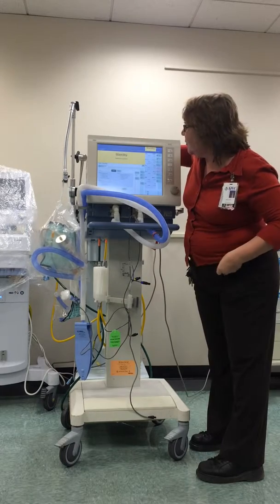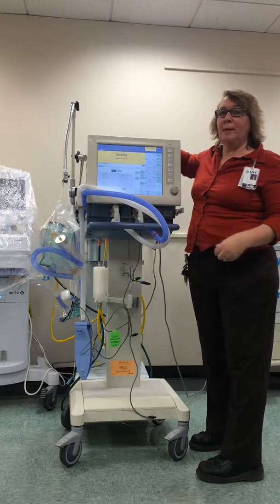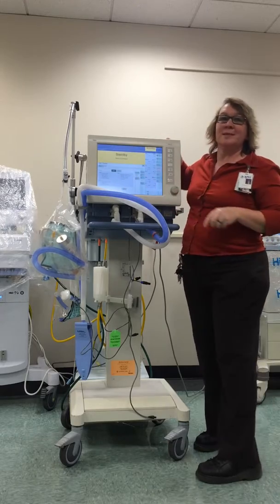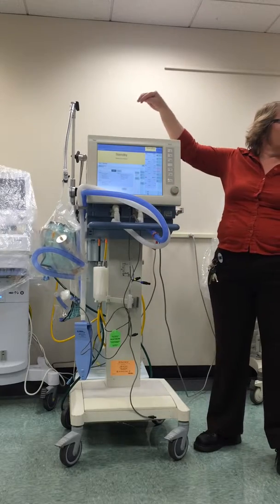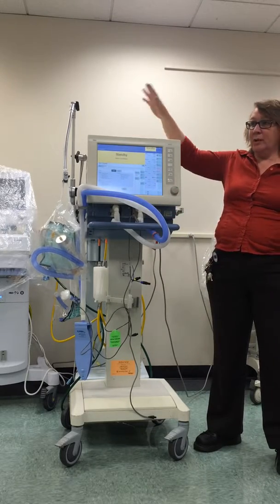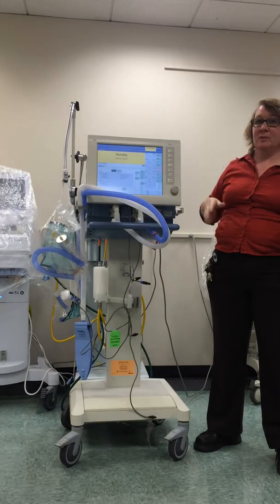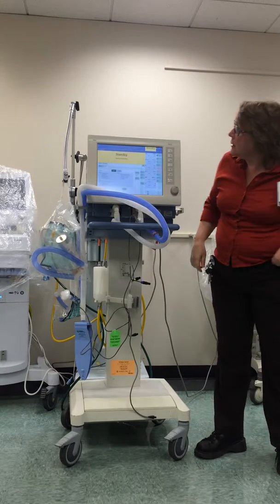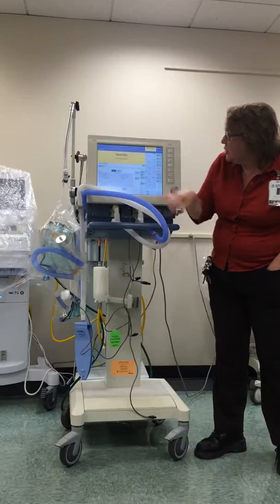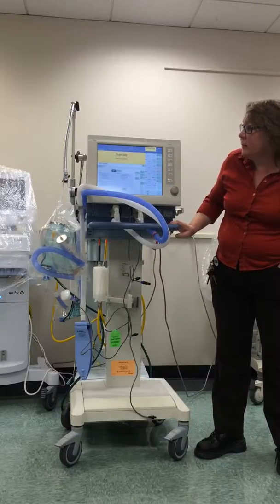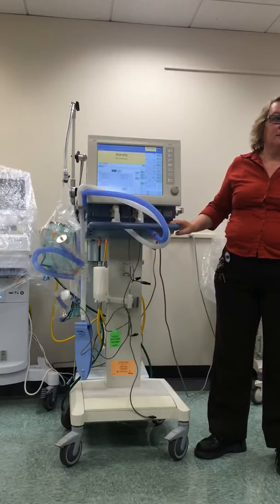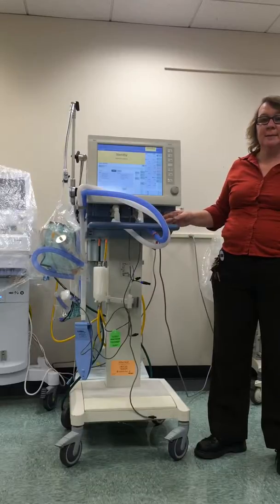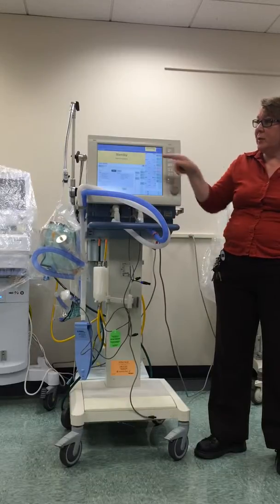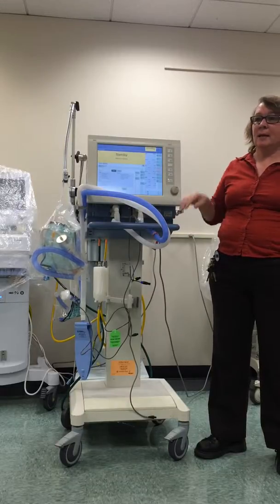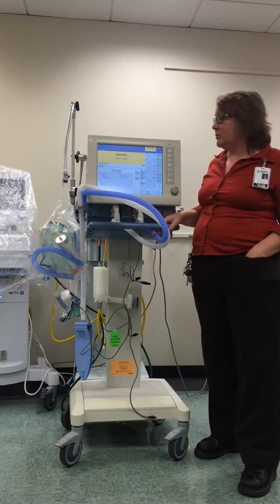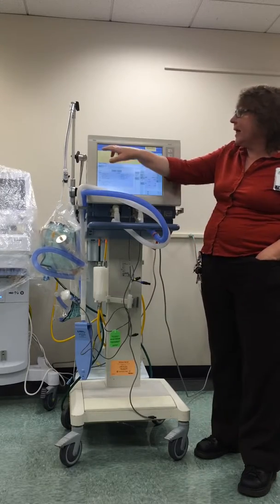So now it's going to do calibration O2 sensor, which takes a moment. And then the next two have to do with the CO2 sensors. The CO2 sensor is not in line, so it will automatically know that and it will stop after this one. But this one takes a minute. So you'll see a little check mark next to the calibration O2 sensor when this part is done. It's pretty straightforward and easy, kind of like the servo is. Just pay attention to what it's telling you. Hit next test when it's at the Neo flow sensor stuff. Okay, now it says calibration okay.